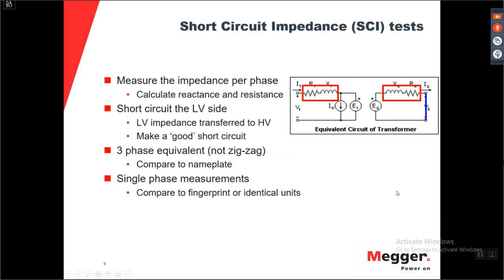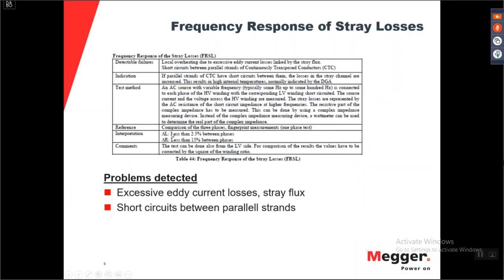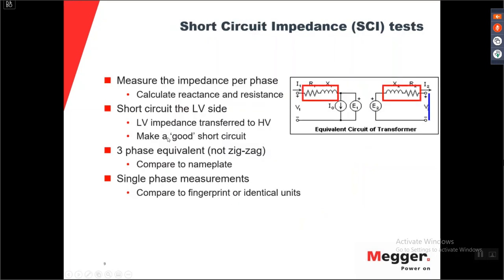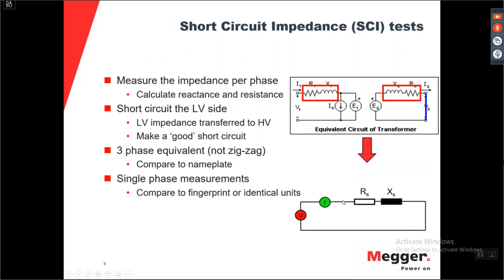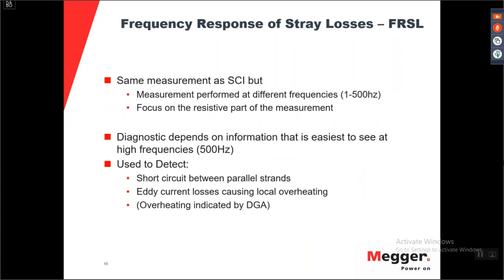So if we now go back to the interpretation, you see the difference in inductance and the difference in resistance we see here. It is actually how these components change with frequency. So what is the difference between the short circuit impedance and the frequency response of stray losses? It is, of course, the same as the short circuit impedance, but you do a variable frequency. So you do 1 to 500 hertz, but you focus on the resistive part of the measurement. The inductance is part of the measurement. You have a definition of how it should behave and what is the accepted value, but the actual part that you're looking for is the resistive, where the allowed change is 15%. And you try to find short circuit between parallel strands.